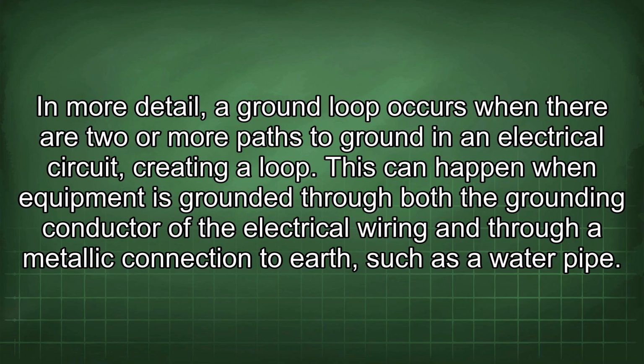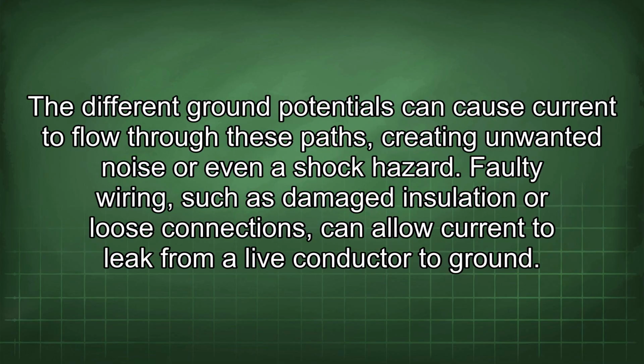In more detail, a ground loop occurs when there are two or more paths to ground in an electrical circuit, creating a loop. This can happen when equipment is grounded through both the grounding conductor of the electrical wiring and through a metallic connection to earth, such as a water pipe. The different ground potentials can cause current to flow through these paths, creating unwanted noise or even a shock hazard.